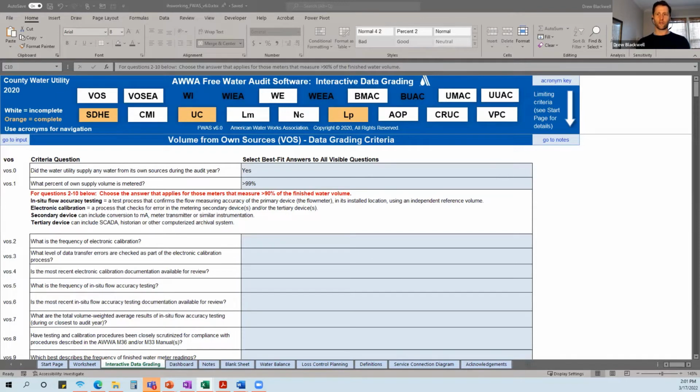No meter is registering flow. It's registering something else. So on a turbine meter, it's registering revolutions. On a Venturi meter, it's registering pressure differential. The computer system is converting whatever that meter is registering to a flow. So there is an electronic signal doing that conversion, and if that signal span is out of range, then that conversion can start to drift a little bit and give us an inaccurate volume that is archived in our SCADA system.